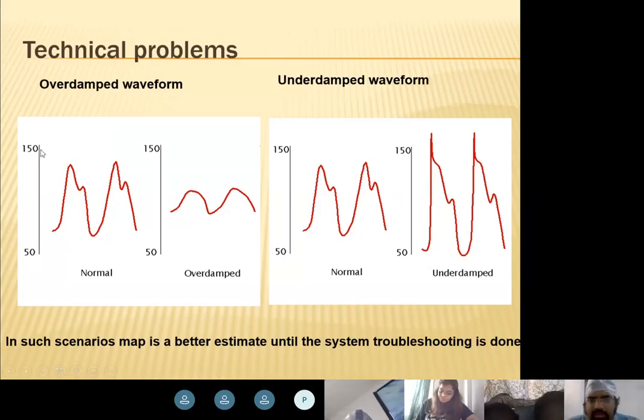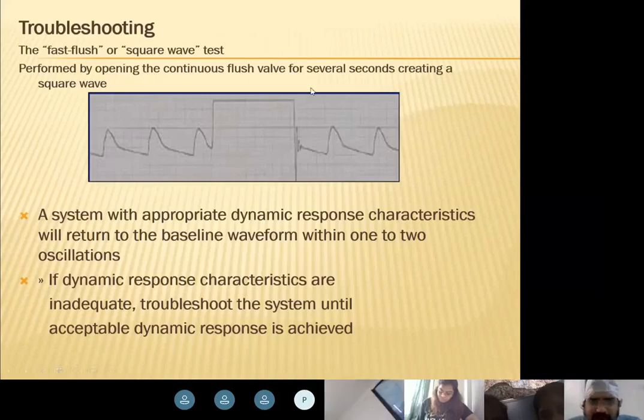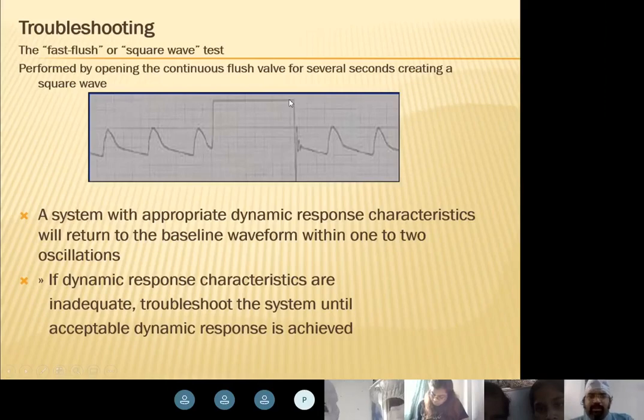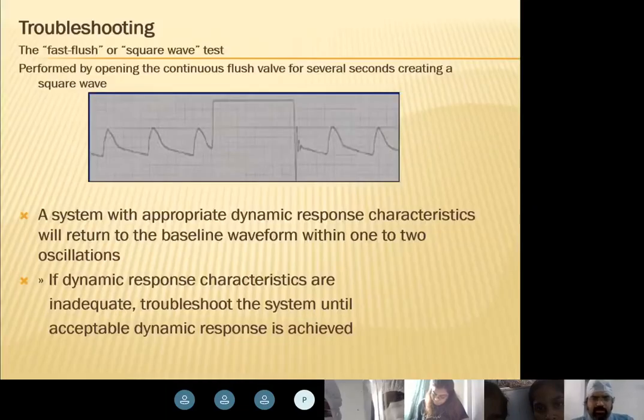अभी 300 अगर एक्सपोज कर दिया तो ये वेवफॉर्म कहाँ जाएगा? ये ऊपर तक आ जाएगा और फिर ये फ्लैट हो जाएगा क्योंकि उसके ऊपर जगह ही नहीं है. 150 के ऊपर जगह ही नहीं है. There is no place above 150. Since there is no place above 150, it will go up and become flat. That is why you get a flat waveform when you're actually doing a fast flush. You see a flat waveform because you have kept the scale between 50 and 150. It cannot go more than 150. So it just goes up and becomes flat. It reaches the pressure of that bag. So in short, if you don't reach the pressure of that bag, you will not see these kind of waveforms.